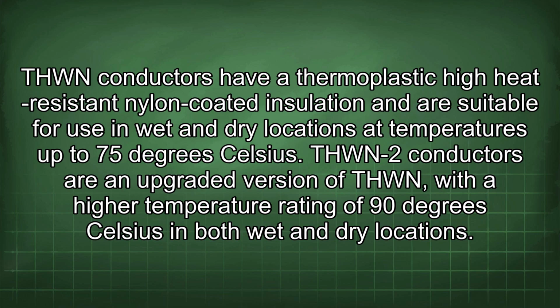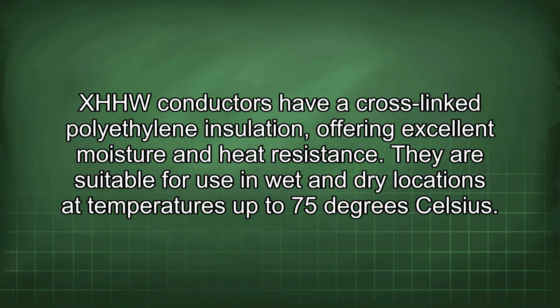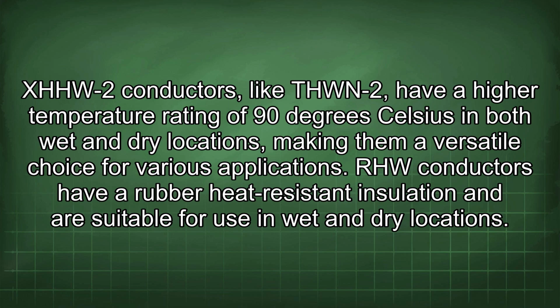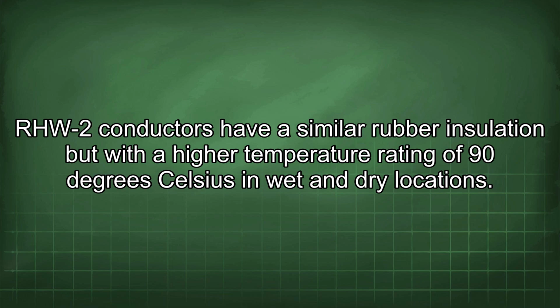THWN-2 conductors are an upgraded version of THWN, with a higher temperature rating of 90 degrees Celsius in both wet and dry locations. XHHW conductors have a cross-linked polyethylene insulation, offering excellent moisture and heat resistance. They are suitable for use in wet and dry locations at temperatures up to 75 degrees Celsius. XHHW-2 conductors, like THWN-2, have a higher temperature rating of 90 degrees Celsius in both wet and dry locations, making them a versatile choice for various applications. RHW conductors have a rubber heat-resistant insulation and are suitable for use in wet and dry locations. RHW-2 conductors have a similar rubber insulation but with a higher temperature rating of 90 degrees Celsius in wet and dry locations.